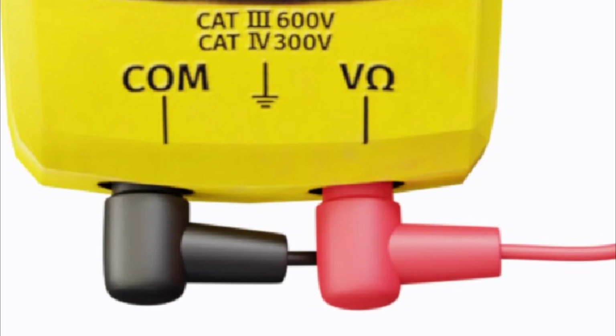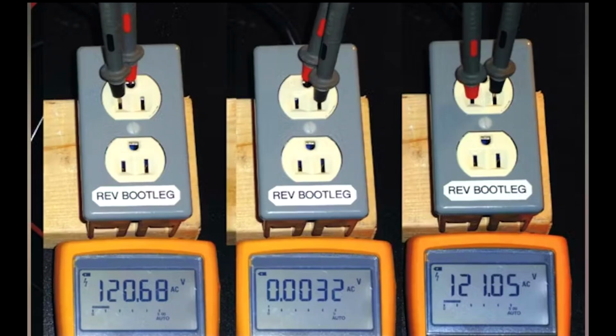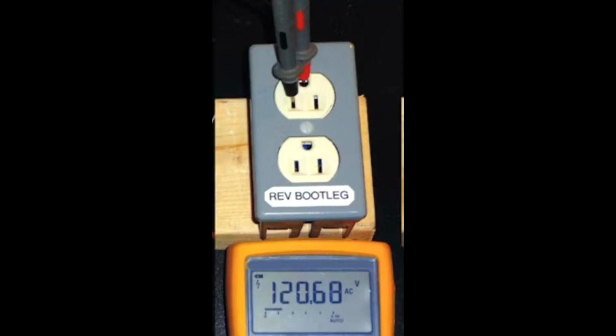So now that you know how to set up your meter, let's go through the steps again. You're going to connect your black probe wire to the COM port. You're going to connect the red probe wire to your voltage port. In this example, we're going to be testing an AC voltage on an outlet. To check AC voltage, you want to run your test in parallel with the circuit. That means that one wire needs to be on the positive, and another on the neutral or the ground. Either will work. In this picture, you can see that they're testing from the hot side to the ground.